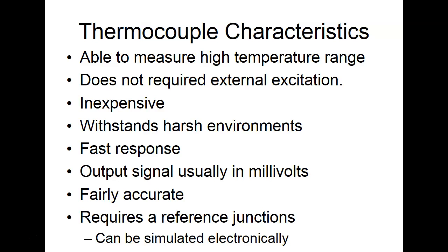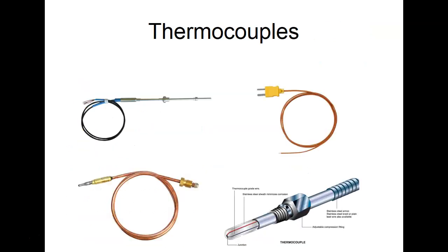And of course, most of the time, like I said, when I first got involved with them, when I was taking a physics class at college, we actually dipped the reference junction in ice water. Now most of your thermocouples, the cold junction is electronically simulated, which is what your meter does. So these are the examples of thermocouples. This is usually the type that you see if you've got gas water heater: you'll see a copper tube that goes up and the thermocouple actually sits in the flame of the pilot light. You don't want to turn on the main gas valve unless the pilot light is lit, right?